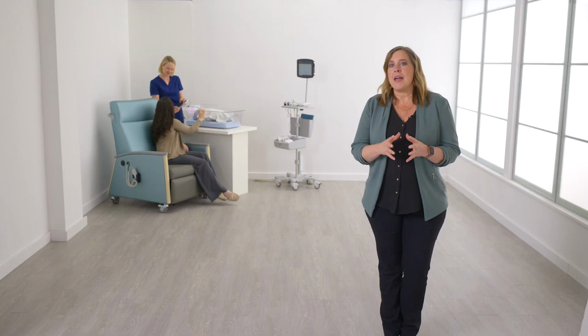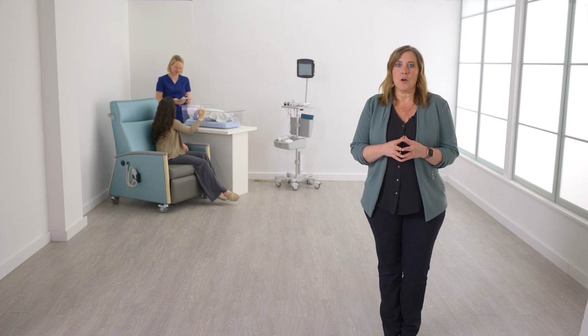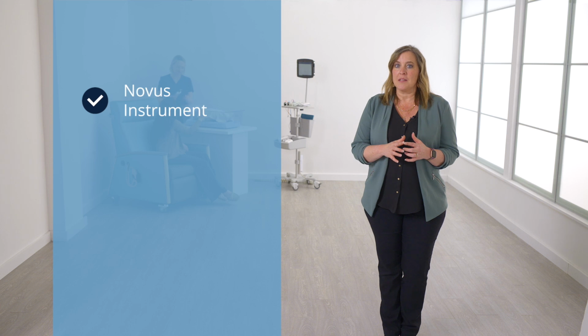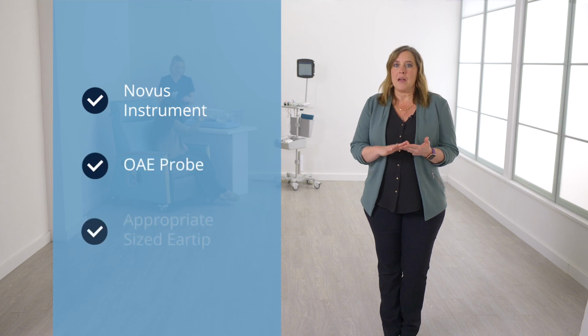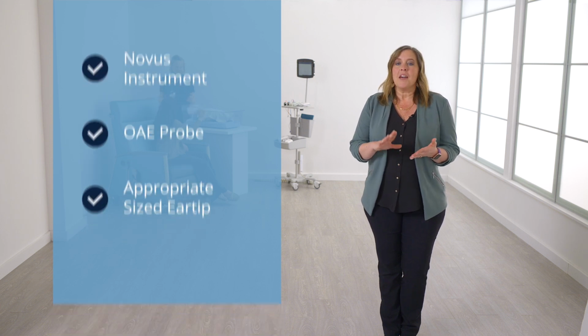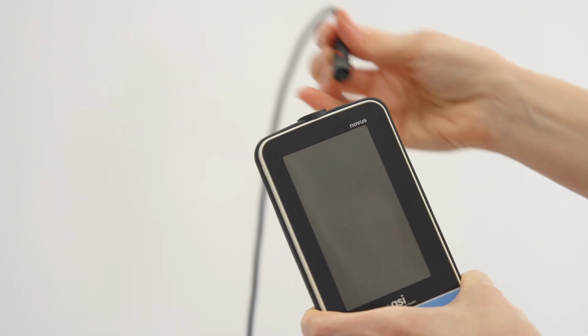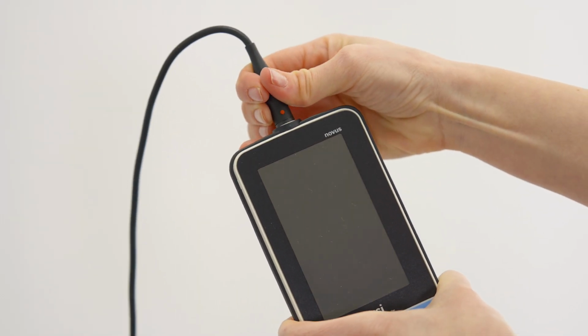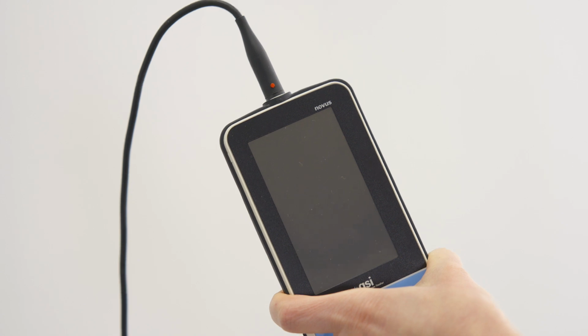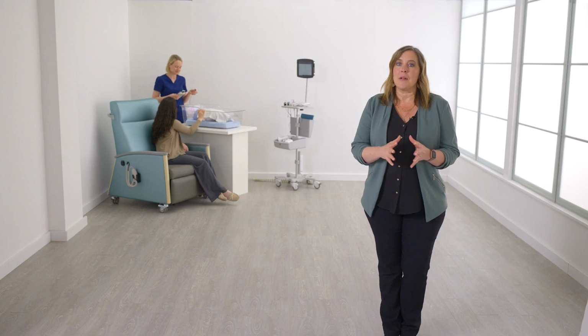To perform OAE testing with the Novus, gather the appropriate accessories and assemble. You will need the Novus handheld instrument, the OAE probe, and the appropriate sized ear tip. Connect the OAE probe to the Novus by aligning the red dot on the cable to the dot on the connector socket at the top of the Novus. Prior to testing, place an ear tip onto the end of the probe.